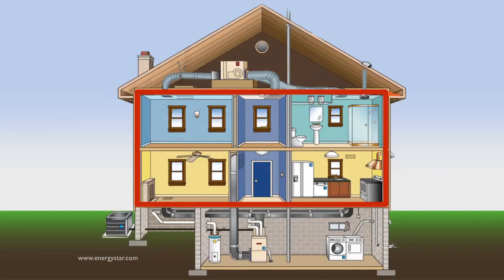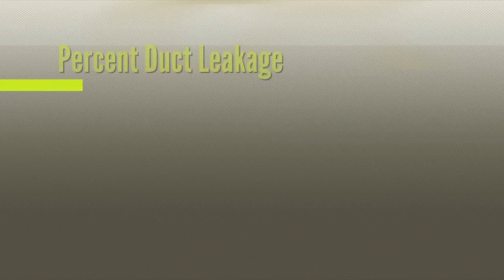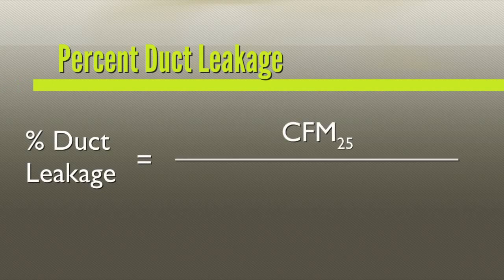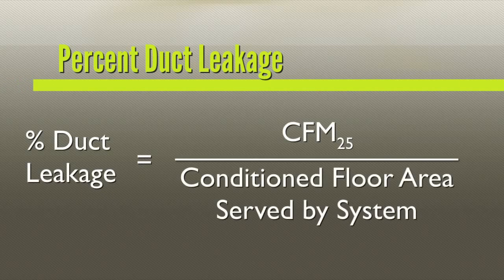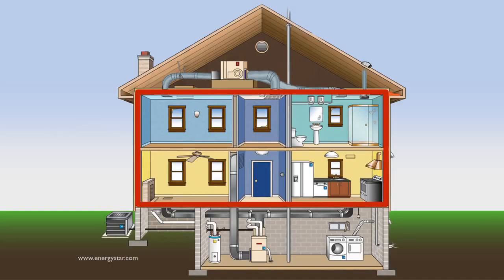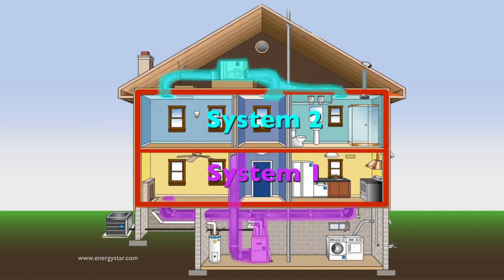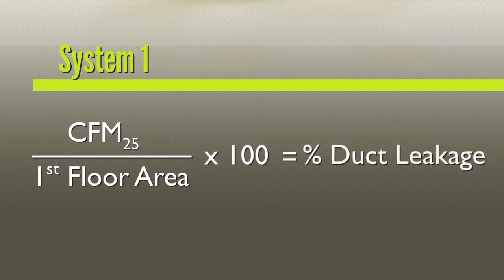In order to compare this number across multiple building types, many programs require you to normalize duct leakage according to the size of the home or HVAC system. For this example, we will compare duct leakage to the floor area of the zone it serves. The percent duct leakage is determined by dividing the CFM 25 by the conditioned floor area that is served by that system. In this home, for example, the first floor area corresponds to System 1 and the second floor corresponds to System 2. Since we are testing System 1, we divide CFM 25 by the area on the first floor. We then multiply by 100 to determine the total percentage duct leakage.